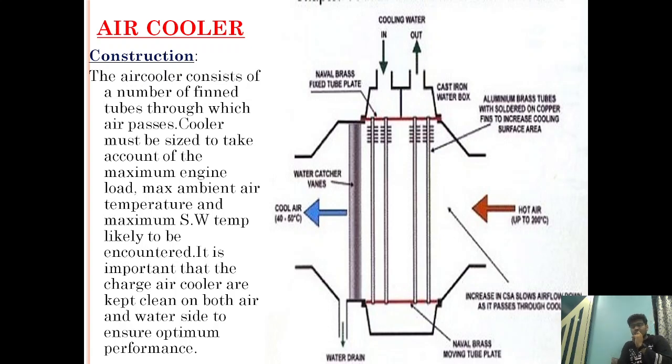Very important to understand. One more time, I will tell you what is happening. Suppose the air is coming from here at 5 meters per second. Now the fins are provided like this. The fins increase the surface area, so they can remove a larger amount of heat in a shorter period of time. Apart from that, they also act as a resistance to the air.